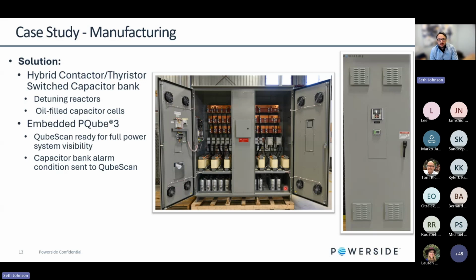So this client loved the data we provided so much that we actually embedded the PQube into the correction solution. So you'll see on the right here, this is the panel power factor controller, and then we've got our PQube embedded in there. And this is going to be able to look at all of the main incoming on all 5 services for this facility, and it's going to give them full power quality data, which they currently don't have at all. And so this was really a win-win for the customer.